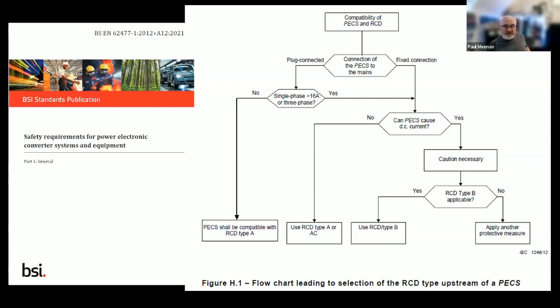One of the interesting pieces in this was that when you apply another protective measure, one of the recommendations was double insulation. So double insulation plus your type B. That way, if your RCD didn't work, you still have the additional measure of double insulation. So there's some fascinating knowledge in the standards that help you consider your RCD protection more.